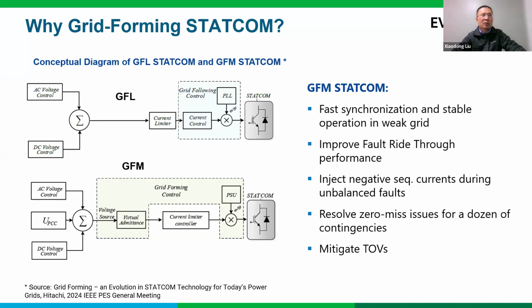So it does not rely on the PLL. We know this is the same behavior as the traditional generator synchronized with the grid. And also its response is very fast. It helps the South Fork Wind connecting to the weak grid, that is the far end of the 69 kV network of Long Island, and achieve very fast synchronization and very stable operation. When there is a fault, it also improves the fault ride-through performance of the wind farm.